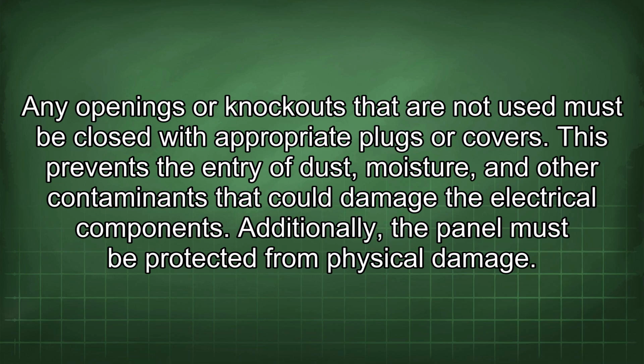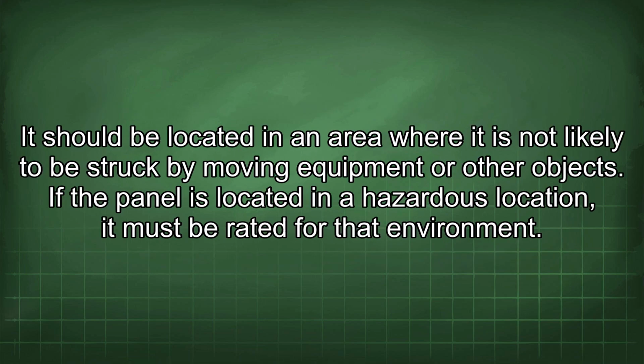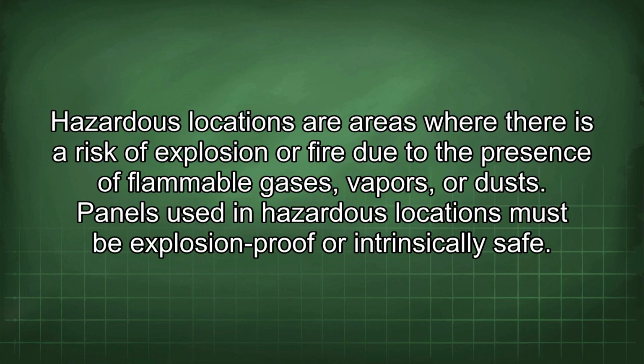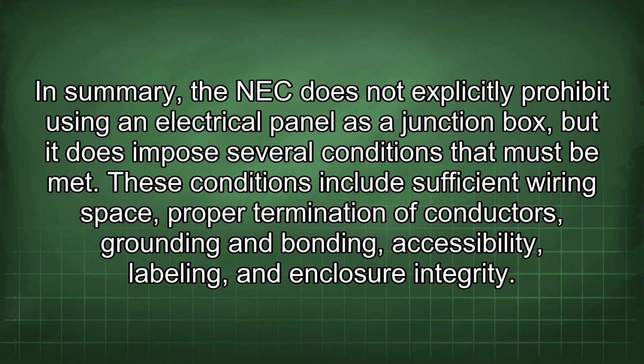Additionally, the panel must be protected from physical damage. It should be located in an area where it is not likely to be struck by moving equipment or other objects. If the panel is located in a hazardous location, it must be rated for that environment. Hazardous locations are areas where there is a risk of explosion or fire due to the presence of flammable gases, vapors, or dusts. Panels used in hazardous locations must be explosion-proof or intrinsically safe. In summary, the NEC does not explicitly prohibit using an electrical panel as a junction box, but it does impose several conditions that must be met.